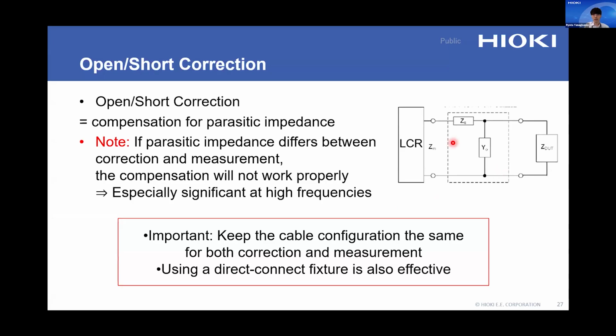By measuring open admittance YO and short impedance ZS, this function compensates for the effect of parasitic impedance in the measurement path. However, there is an important point to note. As demonstrated in this video, changes in cable configuration directly lead to changes in parasitic impedance. Even if correction is applied, the compensation will not work properly if the parasitic component changes. Therefore, it is important to keep the cable configuration as consistent as possible between correction and measurement.